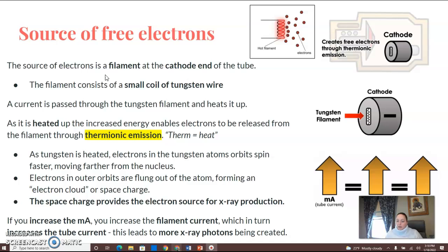This process is called thermionic emission. When you see the word 'therm,' it means heat. As the tungsten is heated, electrons in the tungsten atoms spin faster, moving farther from the nucleus. The electrons in the outer orbits are flung out of the atom, forming an electron cloud or space charge. That space charge provides the electron source for X-ray production.